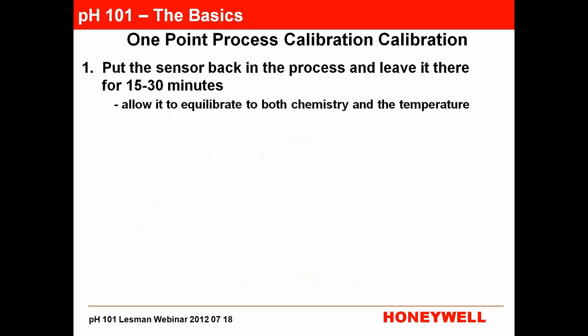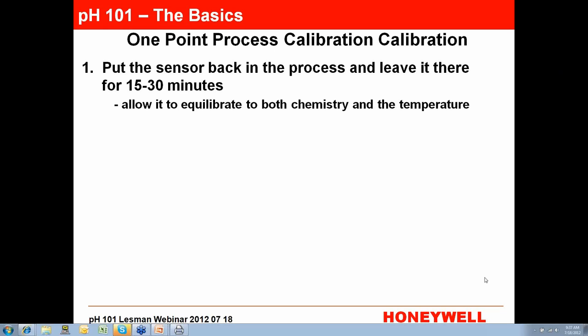To do a one-point process calibration correctly, if you've taken the sensor out and done a two-point calibration, put it back into the process and wait between 15 and 30 minutes — I usually wait 30 minutes — so it can come up to process temperature and equilibrate with the chemistry of the process, so that the liquid junction reaches equilibrium.